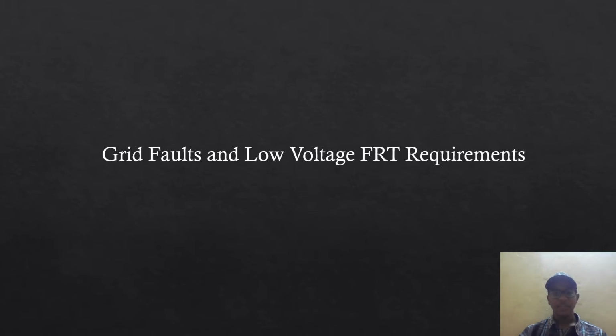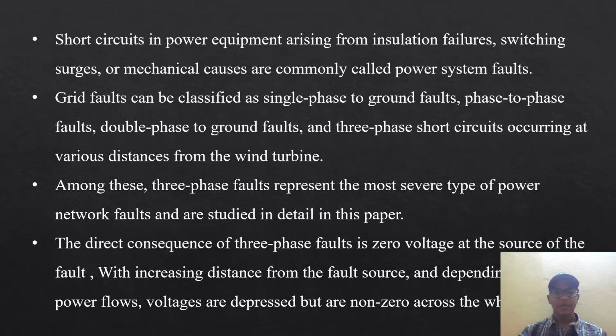Grid faults and the low voltage FRT requirements. Short circuits in power equipment arising from insulation failure, switching surges, or mechanical causes are commonly called power system faults. Grid faults can be classified as single phase to ground faults, phase to phase faults, double phase to ground faults, and three phase short circuits occurring at various distances from a wind turbine. Among these, three phase faults represent the most severe type of power network fault and are studied in detail in this paper.